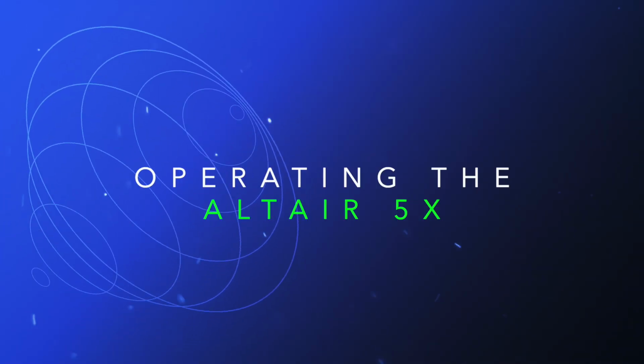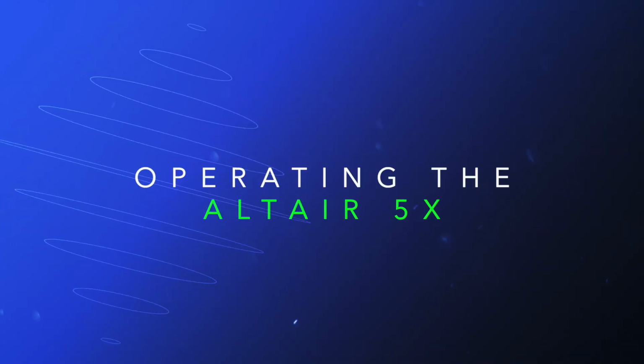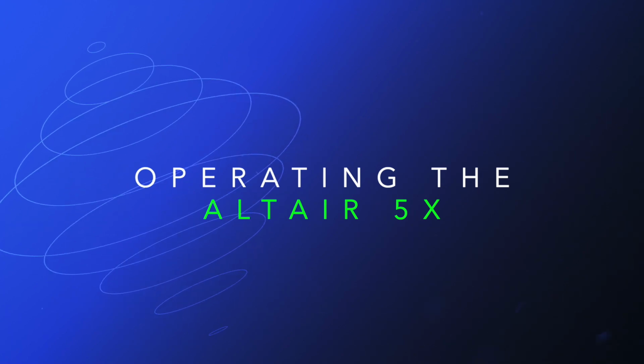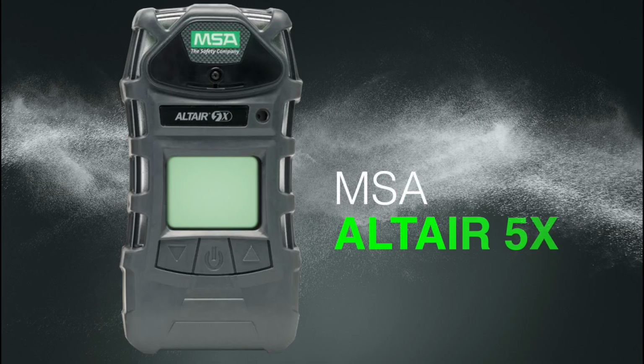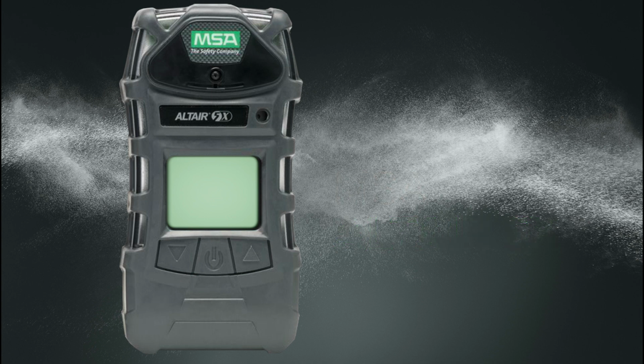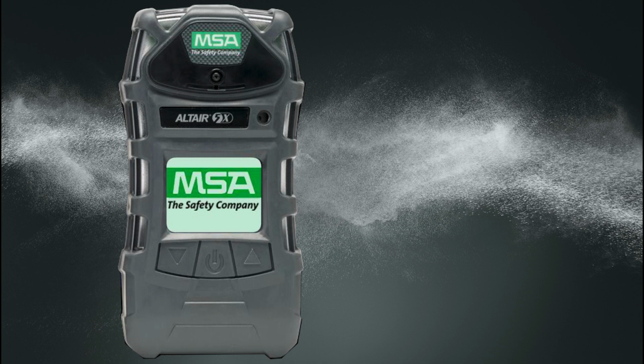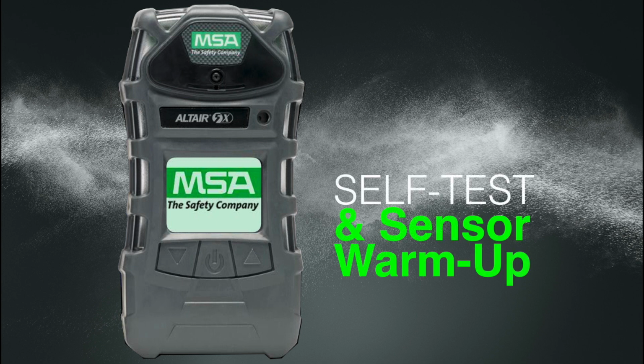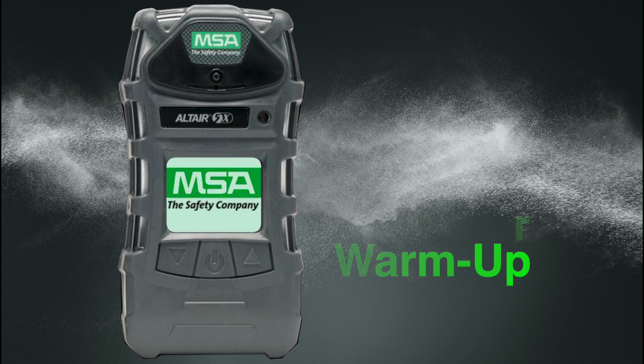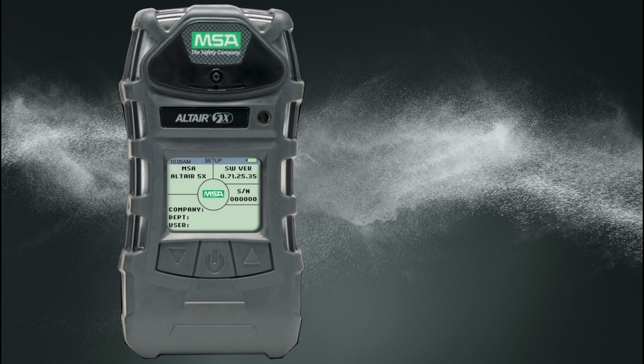The following demonstration for the Altair 5X will happen in real time, demonstrating the actual time required for device startup. The Altair 5X gas detector uses a one-button operation. To turn the unit on, perform the following steps. Briefly press the on-off button to switch the instrument on. Once turned on, the unit will display the startup logo, and perform a self-test and sensor warm-up. During the self-test, the instrument checks alarms and installed sensors. The instrument will display the software version, device serial number, company name, department, and usernames.